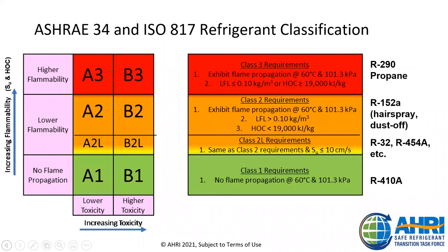And I've been talking about A2L, and I wanna just share with you the refrigerant classification so that you can take a look and see this. When we talk about refrigerants that we're using today, we talk about 410A, and that's considered by ASHRAE 34 an A1 refrigerant. And then we talk about some of the newer refrigerants that are gonna be part of the AIM Act transition. The ones that we're focusing on today are the A2Ls. That will be things like R32, R454B, et cetera.